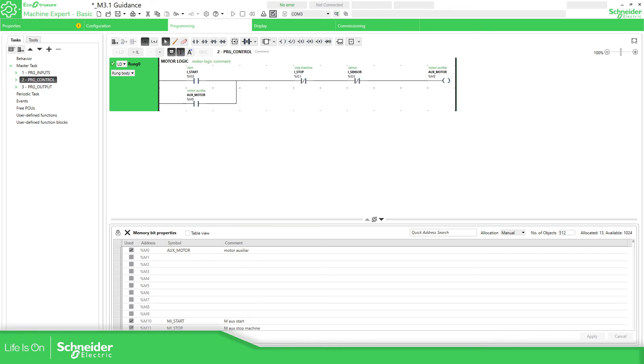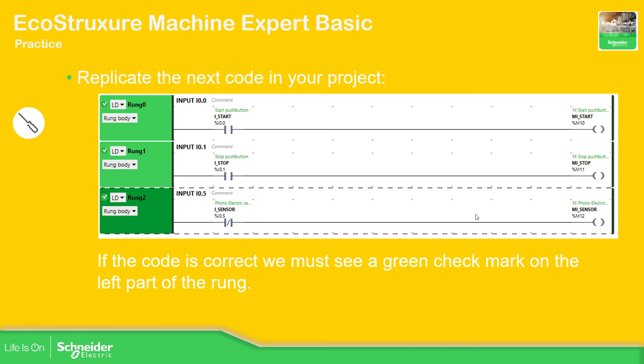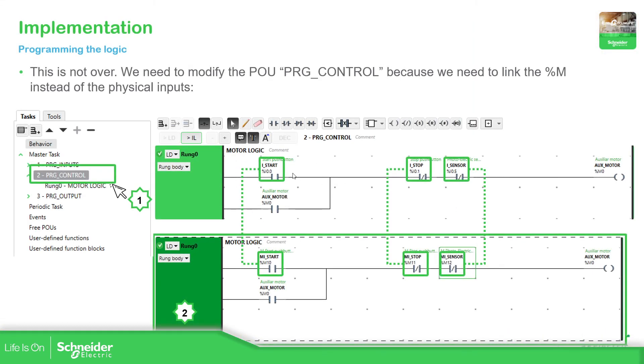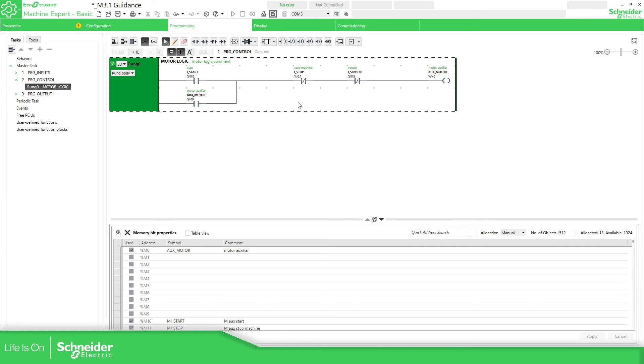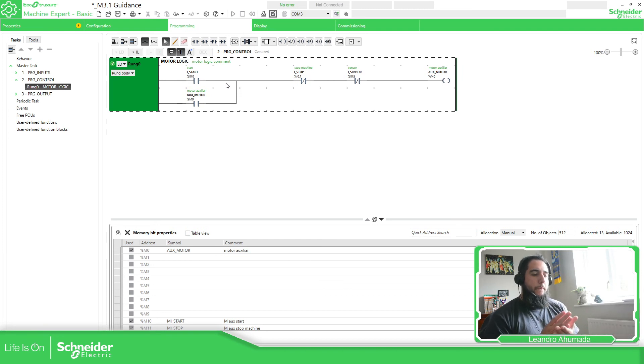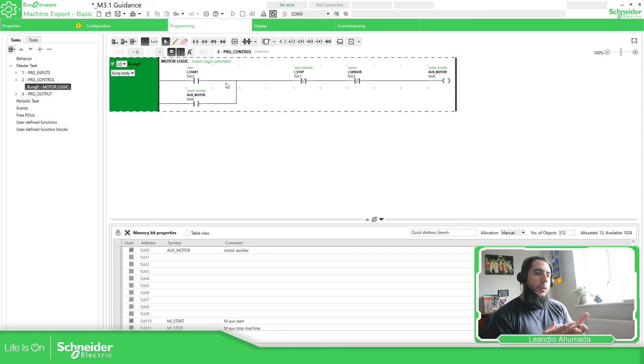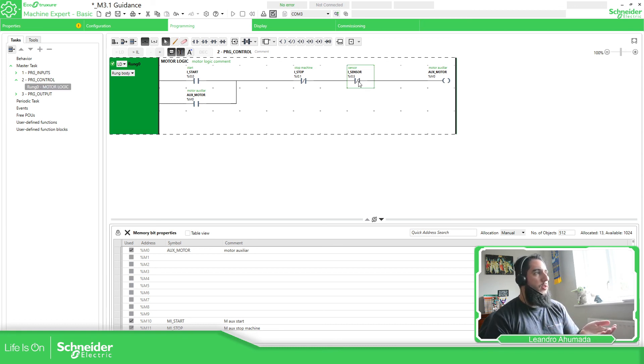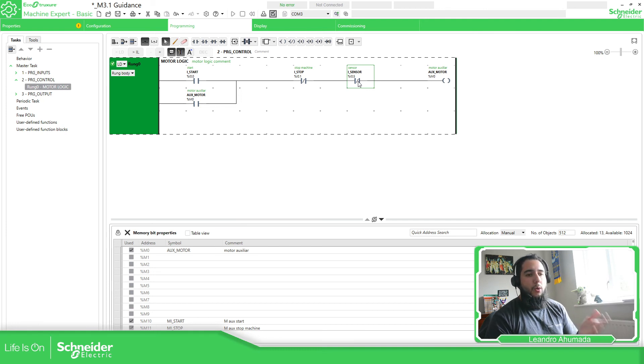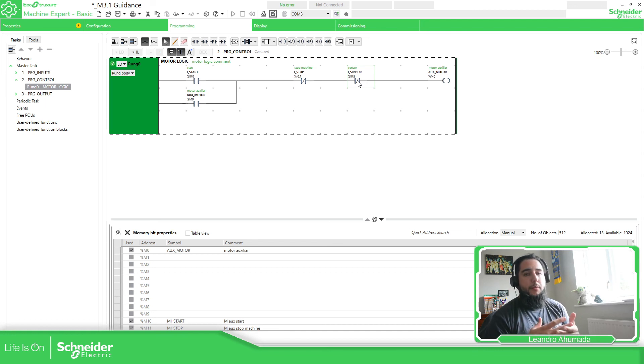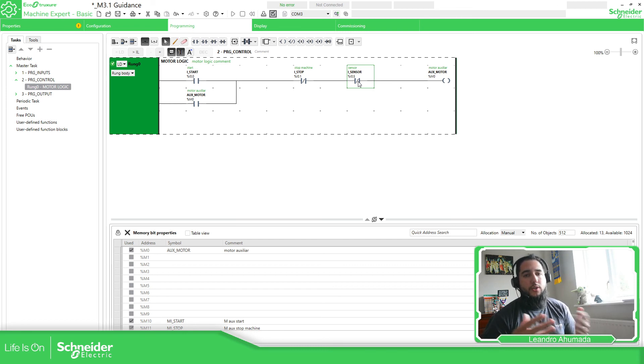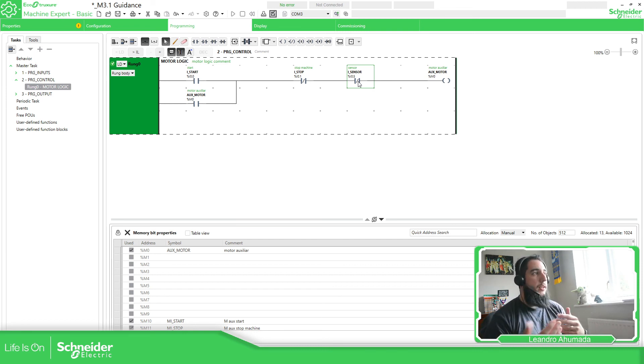So let's go back to the presentation. As mentioned, now what we need to do is change this in the logic that we have on PRG_CONTROL to be like this. So let's go back to the code over here and change. If we don't make these auxiliary variables for the inputs, the thing is that we need to change this sensor over here from normally closed to normally open in order to make it work. And if you have used this variable in different parts of the code, you need to manually change that. It's going to take time. That's why we have made this.